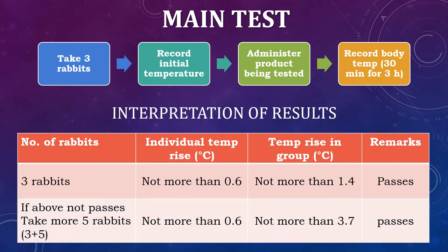If the individual temperature rise is greater than 0.6 degree centigrade and the sum of the three rabbits' body temperature rises is greater than 1.4 degree centigrade, then take an additional five rabbits and perform the same procedure. Now with the original three plus the additional five, there are 8 rabbits total. For these 8 rabbits, if the individual rise is not more than 0.6 degree centigrade, and their sum of temperature differences is not more than 3.7 degree centigrade, then it passes the test. If either the individual rise exceeds 0.6 degree centigrade or the group sum exceeds 3.7 degree centigrade, then we can say that pyrogen is present.